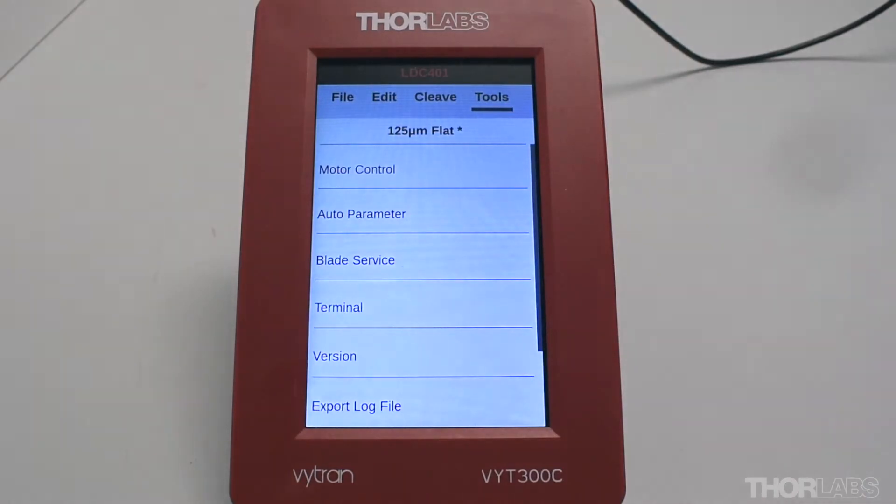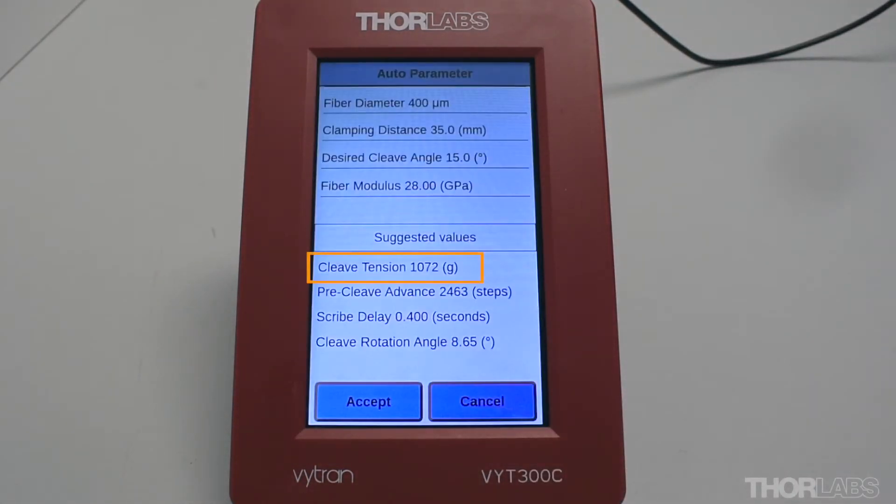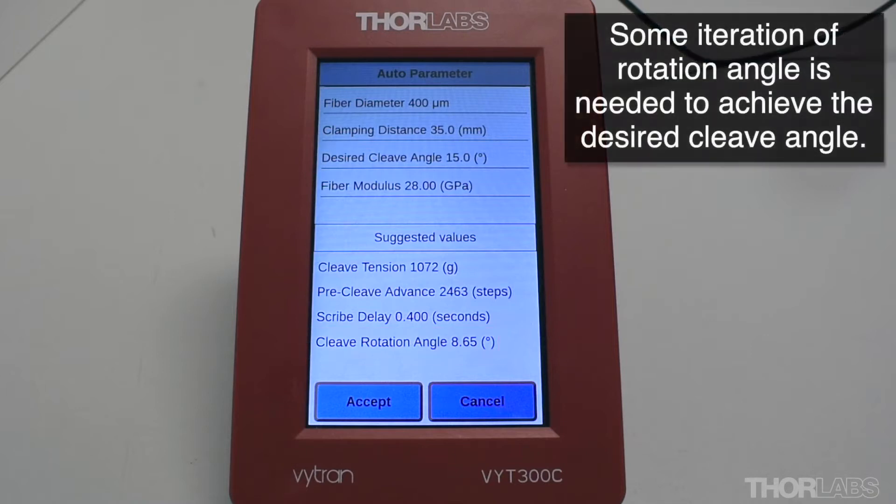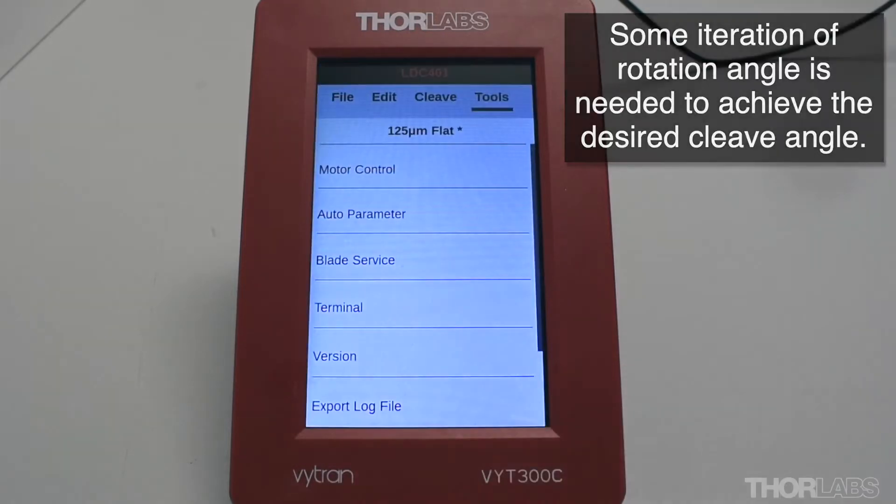Use the auto parameter tool to suggest an appropriate axial fiber tension. The controller will also determine the angle for the rotation stage required to achieve this cleave. However, it should be noted that some iteration from this suggested starting value may be required, especially for large cleave angles.